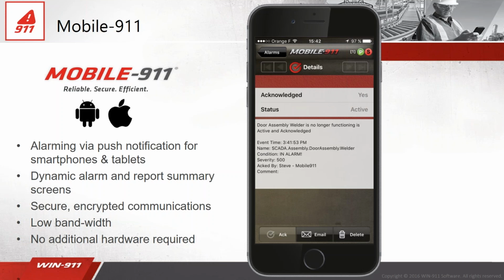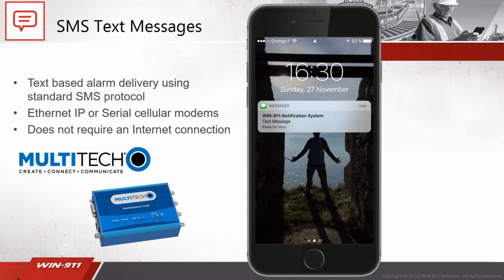So that's it for mobile. So let's go to SMS. So SMS, like I said, we're using a new modem. We're doing the Ethernet IP. Again, think of the same exact, there's a picture of it right there. It's the same looking modem. It just has an Ethernet port on it, and when you plug it into your network, it gets a static IP address. Well, you have to configure that, and then you tell WIN-911 to connect to that modem over that IP address. And again, you're not physically connecting it to the machine.